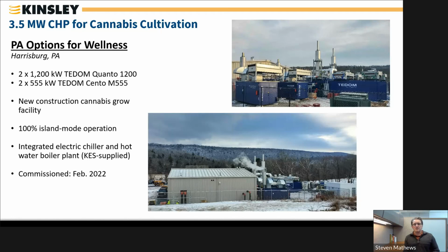We installed four different CHP systems from our manufacturer, the TEDOM Group—two 1.2 megawatt systems and two 555 kilowatt systems. We did this to provide N+1 redundancy, meaning if one system goes down, there's a backup that can provide complete power to the facility. This is a requirement because this facility is not parallel to the grid.